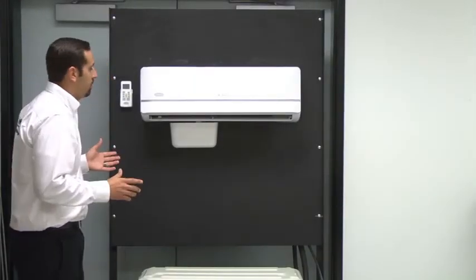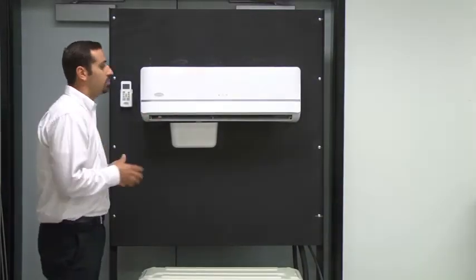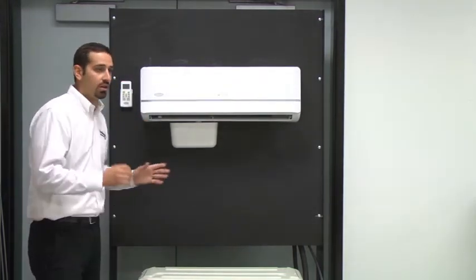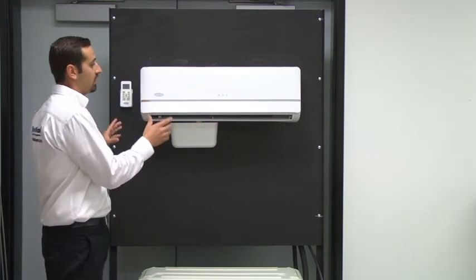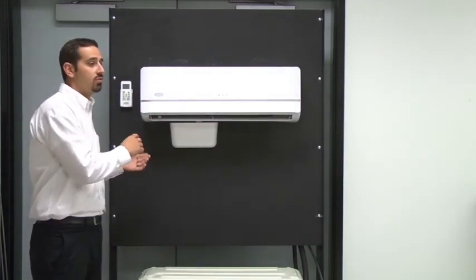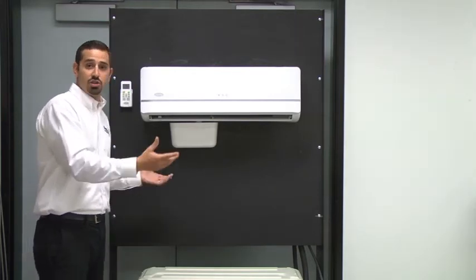All right now we're all buttoned up, pump's installed, tubing is ran. What we need to do now is test the unit so while you're packing everything up, clean up your drop site, just make sure you dump a little bit of cold water in the drain pan that'll drain into the reservoir, the pump should turn on and eject the water.